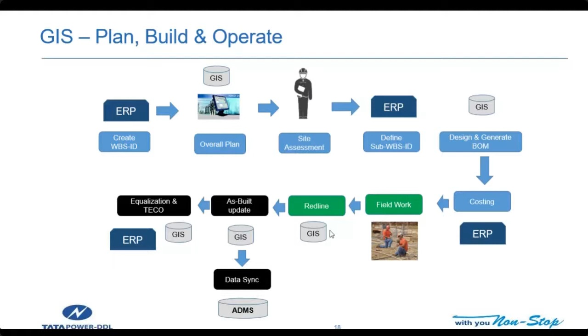Then the field work is done. At times there are deviations witnessed from the original plan, so project members sketch out the deviations, which we call redlining. Based on this input, the as-built data update is done in the GIS system, which then goes on one end to the operation system, the ADMS, and on the other end is reconciled with the financial asset register of the organization. Then a scheme is technically completed. This takes care of all new field works being updated in the system, so that the system remains live.